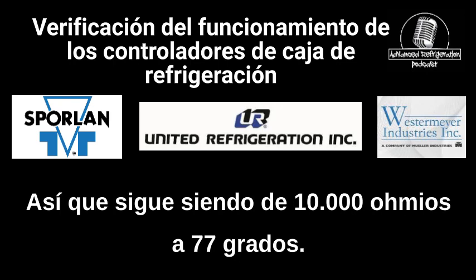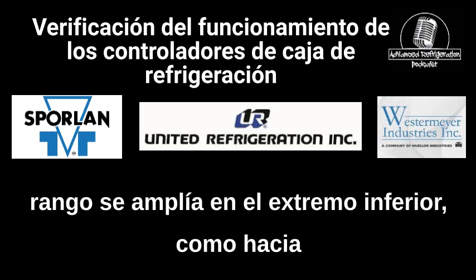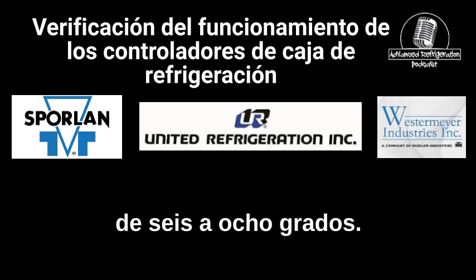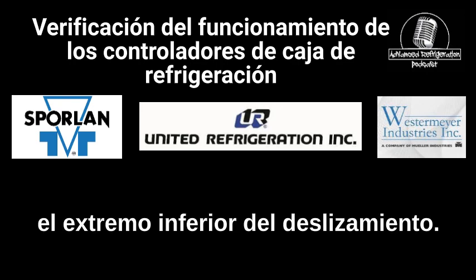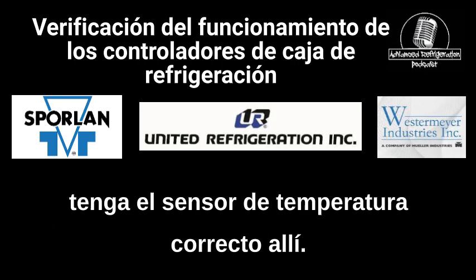So it's still 10,000 ohms at 77 degrees, but as the temperature starts coming down, the range widens at the lower end, towards when it's trying to maintain temperature, by anywhere from 6 to 8 degrees, just because of how the resistance works on the lower end of the glide. So make sure that you actually have the correct temperature sensor in there.